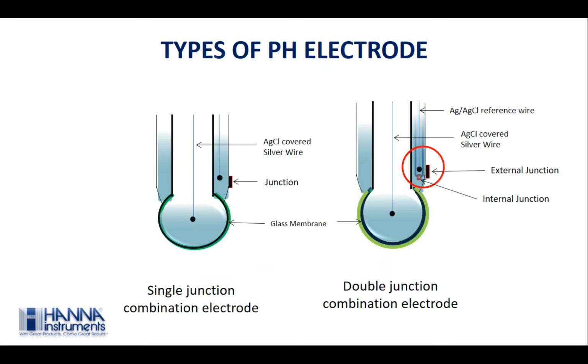The outer ceramic junction is a porous substance which allows the electrolyte to flow out of the electrode with a constant speed. This similar flow rate is not always suitable to all types of samples. Sometimes in low conductive samples, the ceramic junction electrode will not give a fast response, and the ceramic junction is susceptible to get clogged in highly contaminated samples. Due to this fixed flow rate, you need to have different types of junctions.